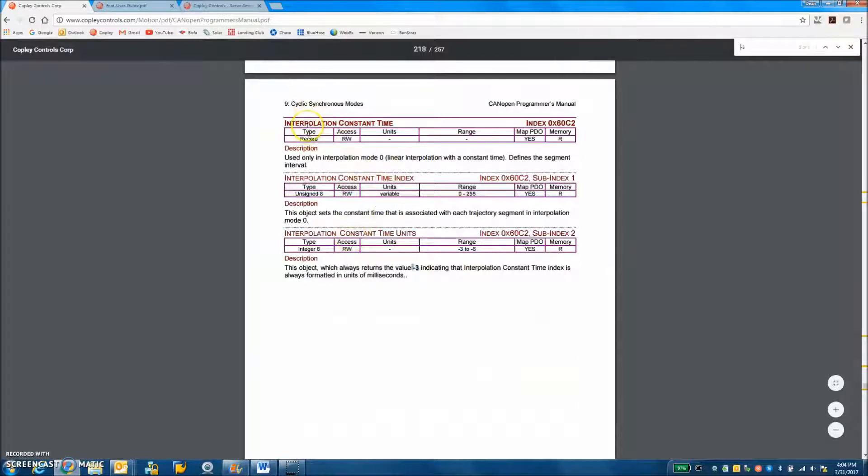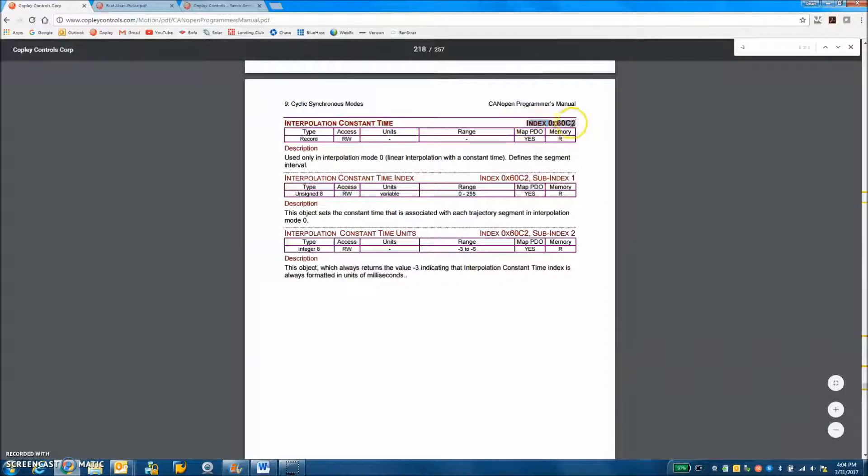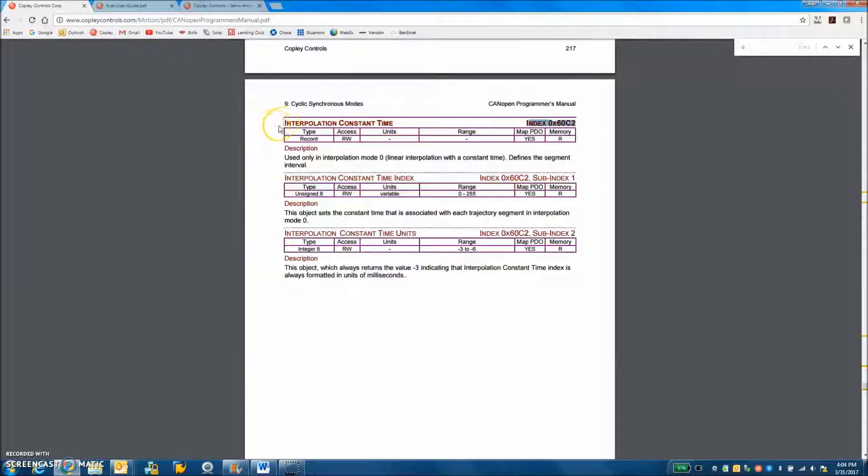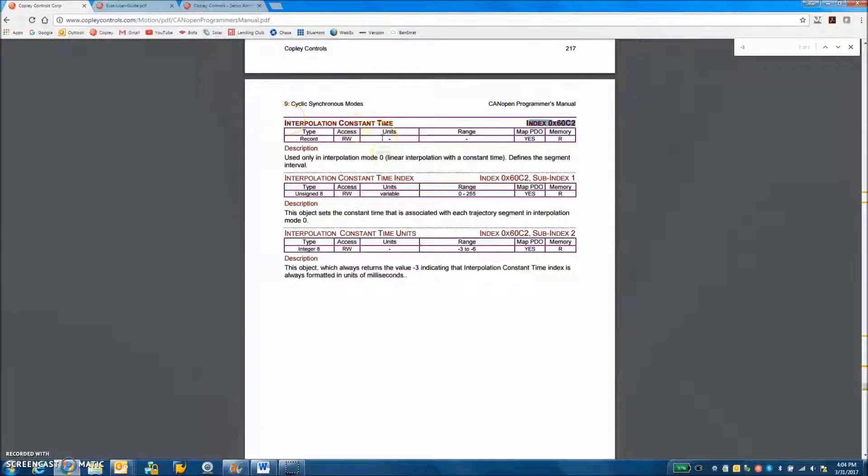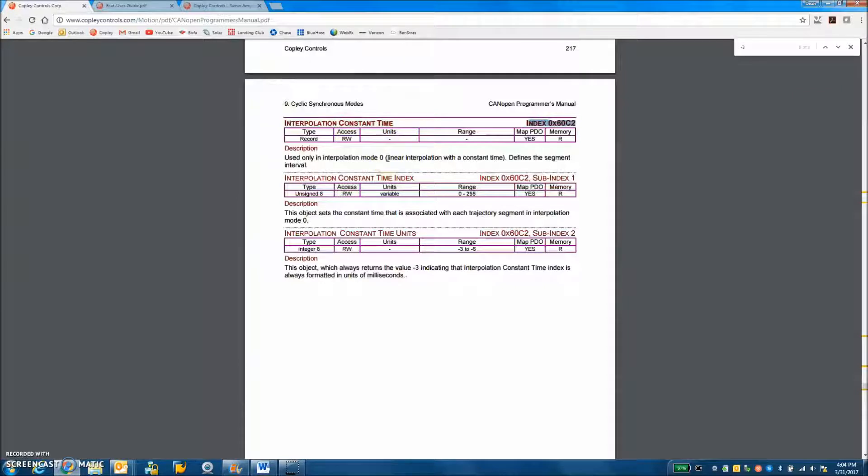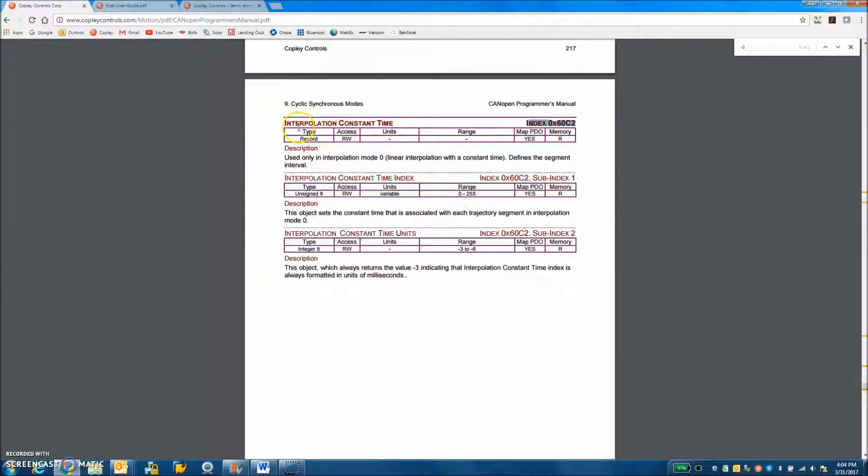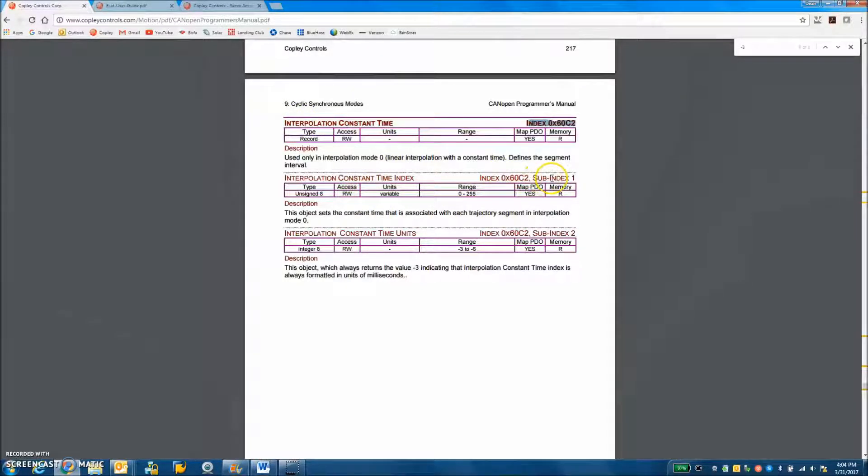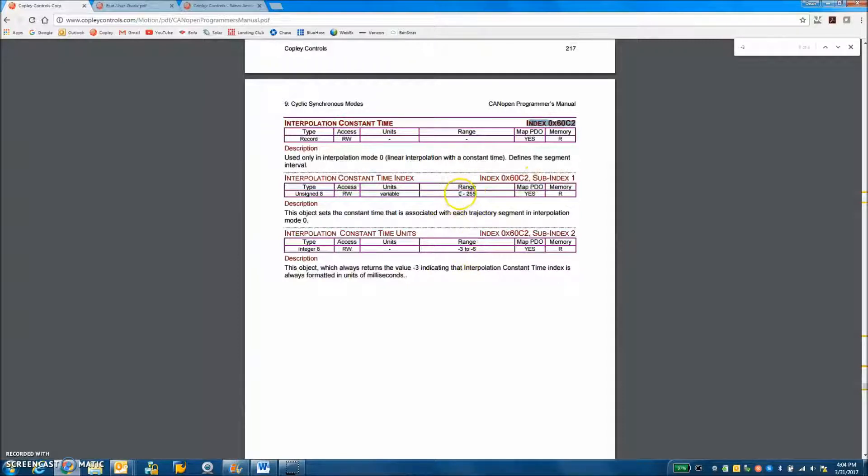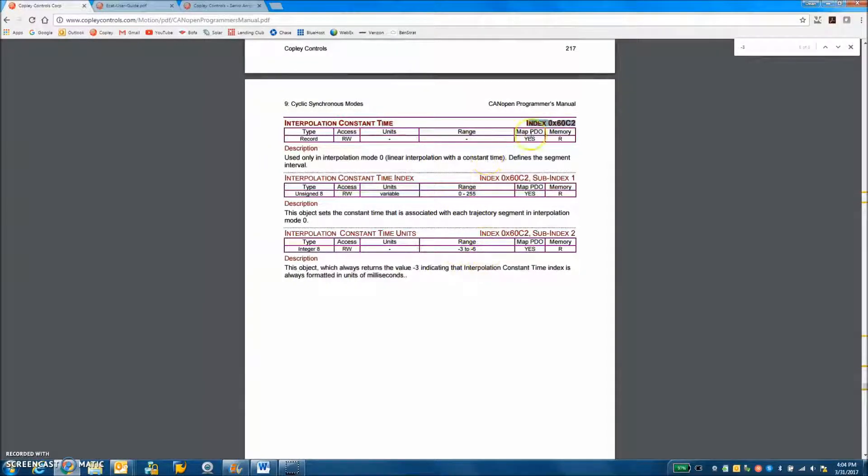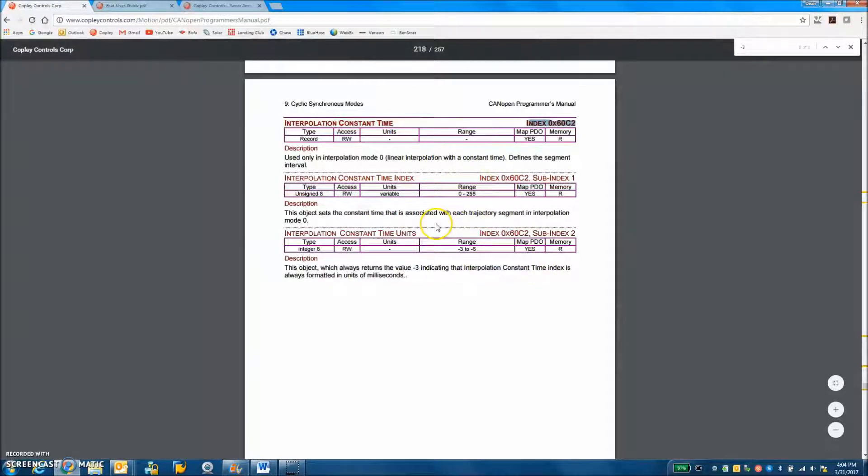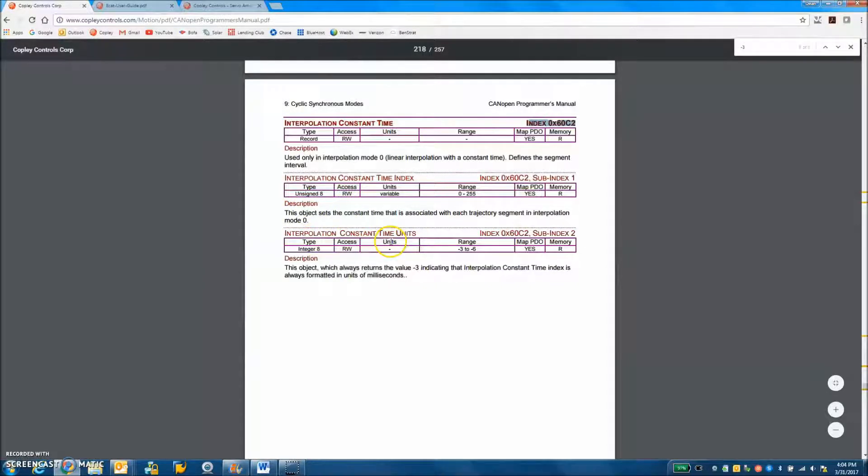So I just wanted to point out that when you're using a step net in open loop micro stepping, you may send your position command every millisecond or whatever. But we like to do interpolation because we close the position of every 250 microseconds. So you need to set the time that you're going to send your update in the subindex one. It's like one times 10 to the minus three is one millisecond. So you've got to set the subindex one and two in order to get the drive to do the interpolation properly when doing open loop micro stepping.